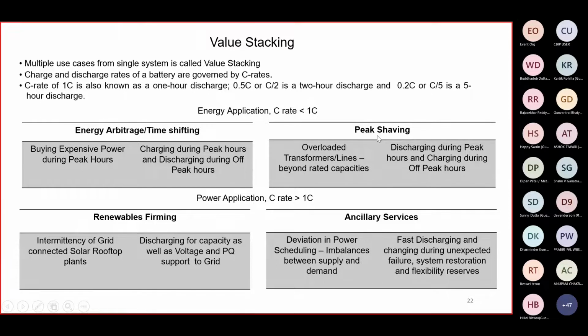And for power applications, which are like ancillary services, where we need a very fast discharge and charging because of an unexpected failure or system restoration, or if ramping support is required, or there is a sudden drop in the renewable output, these are the C rates which are greater than 1C, and that's under the power applications. So based on the applications, the chemistry is chosen and the cells are designed. The C rate and the multiple use cases are very important, because if we are designing, say, for peak shaving, then when peak shaving is not being used, we can use it for energy time shifting, where we charge during the off peak hours and we discharge during the peak hours, when the prices are really high, or the system marginal cost is high. So we can design it for multiple use cases.